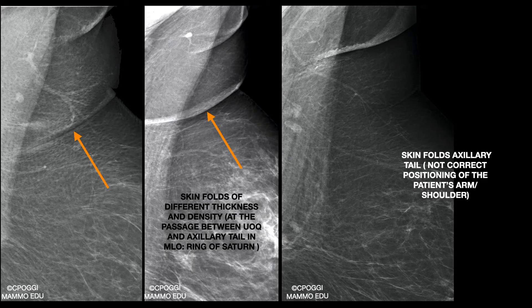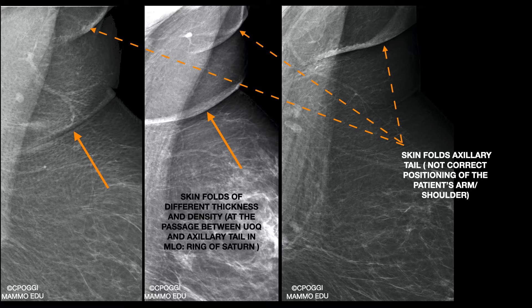A typical ring of Saturn artifact is found exactly at the passage between upper outer quadrant and axillary tail; it is due to a not effective stretching out of the tissue in this area, and is not always resolvable. On the contrary, these ones are due to improper positioning of the patient's arm and shoulder.